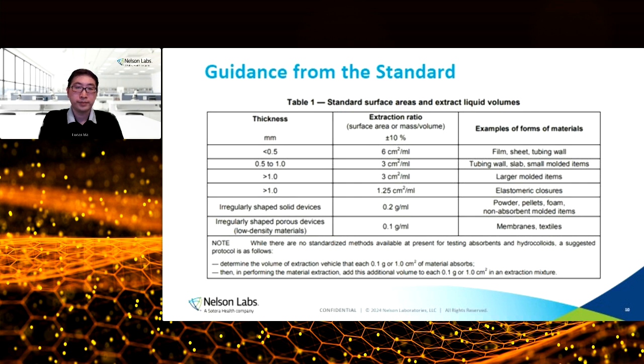Yeah, exactly. So if, oh, sorry, go ahead, Audrey. Yeah, I was just going to add to that, when we think about worst case scenarios, it's important that every facet of medical device examination is a different worst case scenario. So, you might have a worst case scenario for sterilization and a worst case scenario for your routine monitoring, but the worst case scenario for biocomp may be something different.